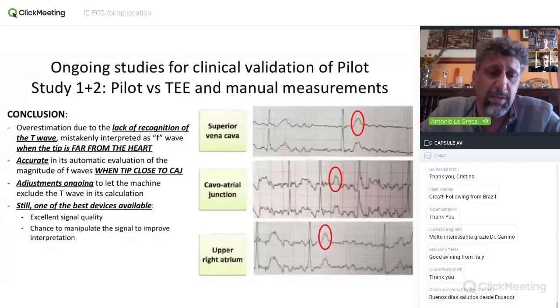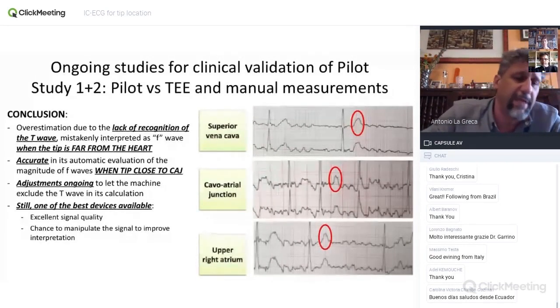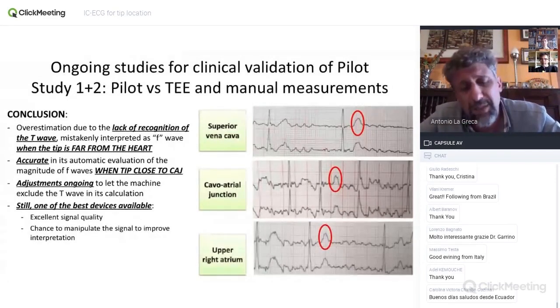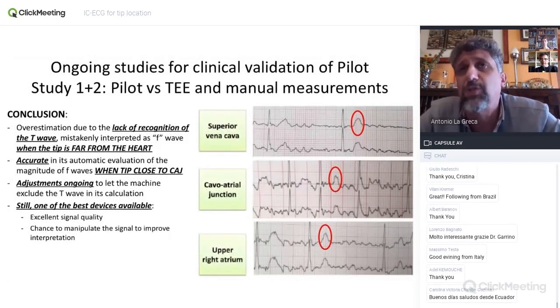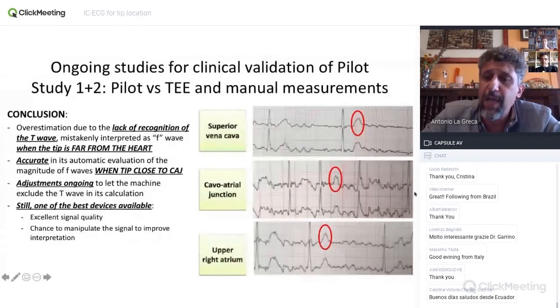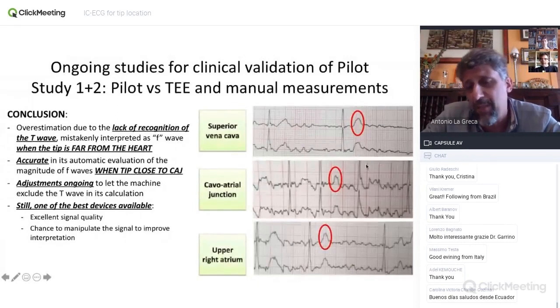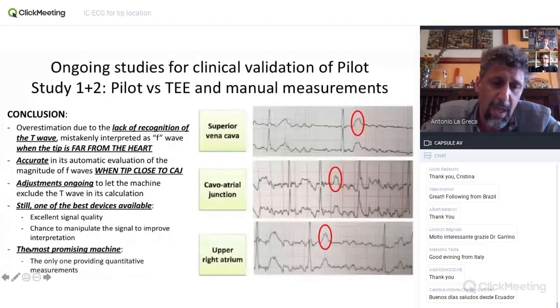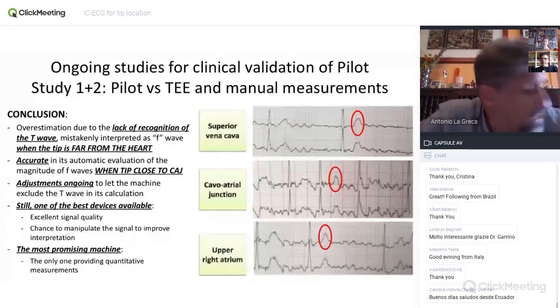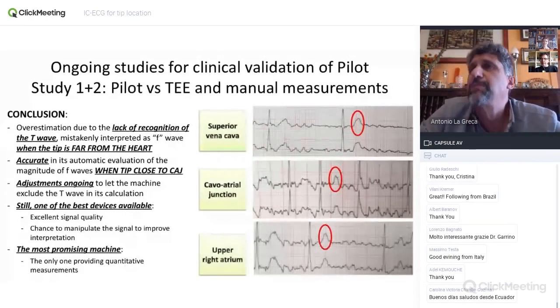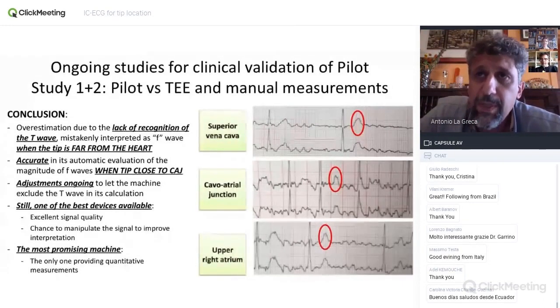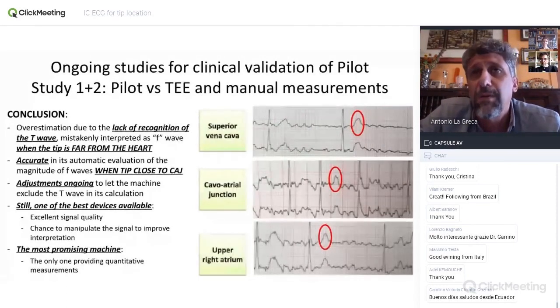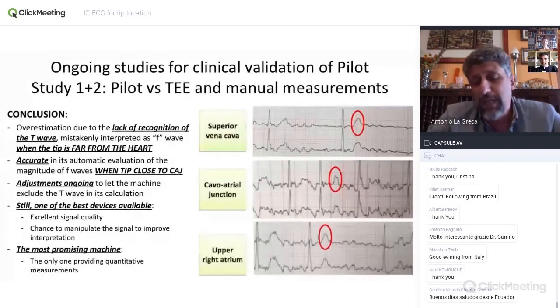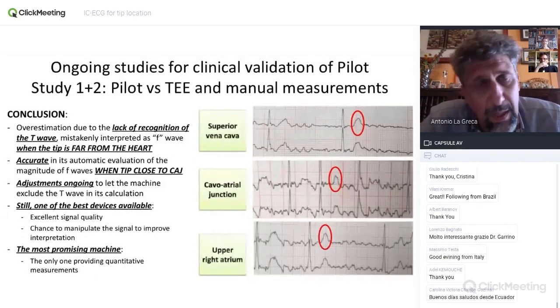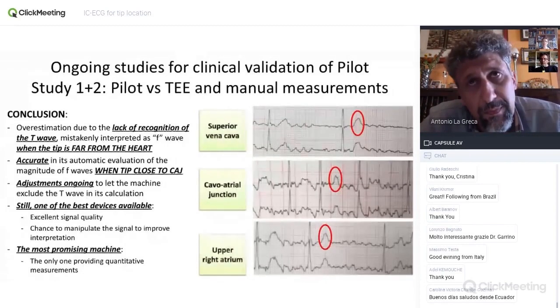the pilot remains one of the best devices available because it gives you an excellent signal quality and the chance to manipulate the signal to improve interpretation, such as when you want to increase the amplitude of the F waves to better see them as compared to the QRS. Still, it is the most promising machine because it is the only one providing quantitative measurements, on which we are working to give a standardizable parameter to let the operator use the machine to automatically detect the atriocaval junction position.